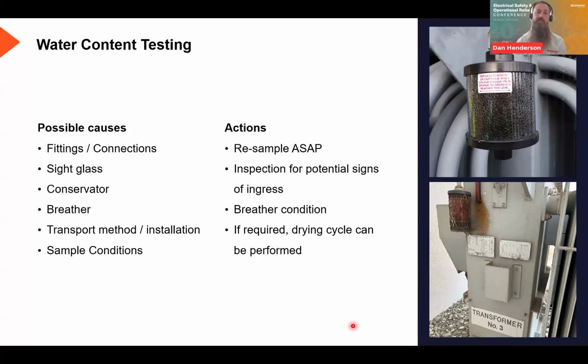I've had it where the batch sample that filled the transformer was all fine, but when it's been transported to site for installation, whether it's in a construction project, the radiators might be transported separately, likewise the conservator, the pipework, and as they're installed, if it's not done in a satisfactory environment, there's potential there where you could get water ingress, which again can be difficult to detect and pin down where that happened if it's not tracked and done properly in the installation phase.